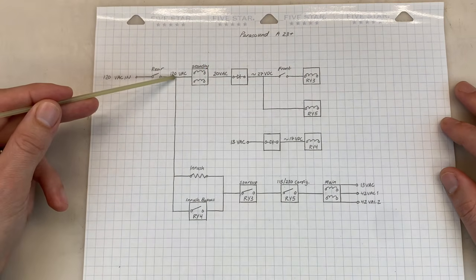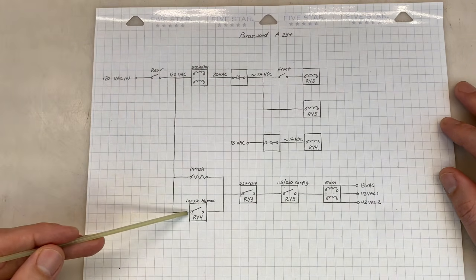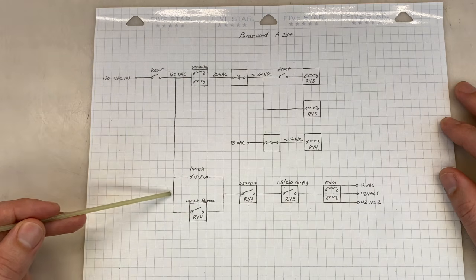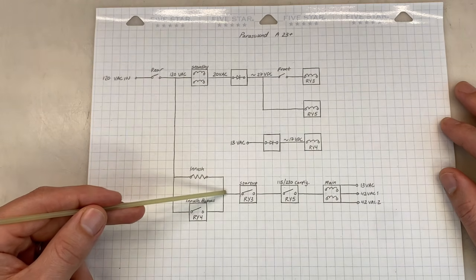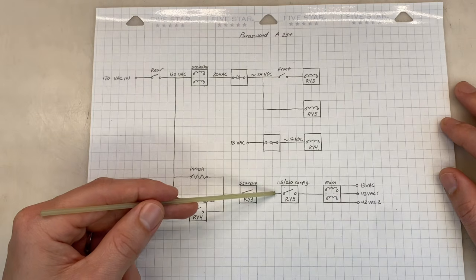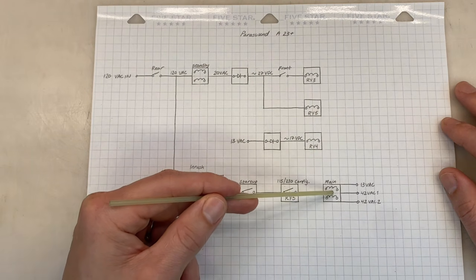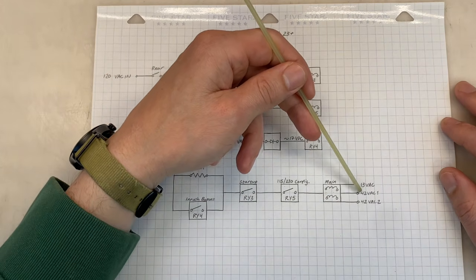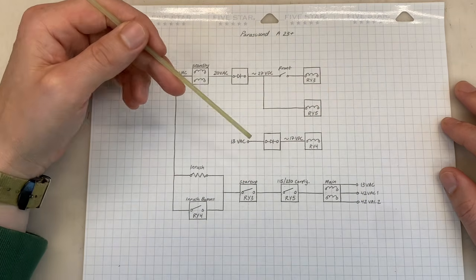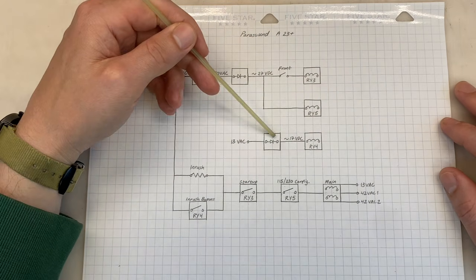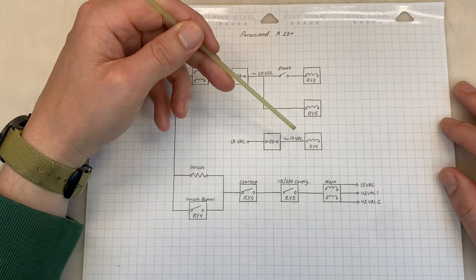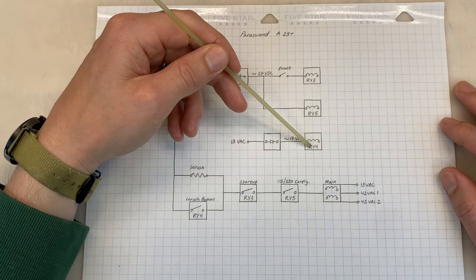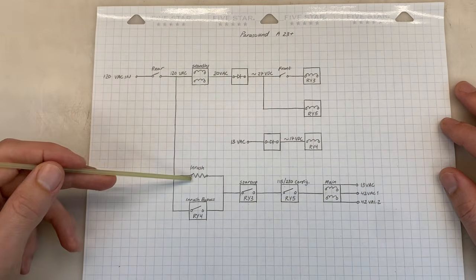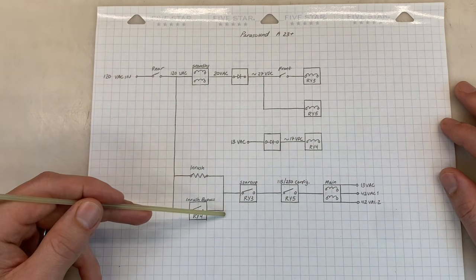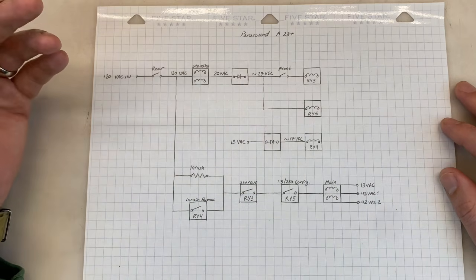Now let's come back to our second AC path. First, if RY4 was energized, it will travel through these contacts, but it's not yet. So it'll travel through this inrush current limiter. It'll then travel through the contacts of RY3, contacts of RY5, and finally it should energize the main transformer. Once this is energized, it will produce 3 voltages, 13, 42, and 42. The 13 volts AC will be rectified, which should produce something like 17 volts of DC. And this will energize relay RY4. Now that RY4 is energized, we can bypass this inrush current limiter, travel through the contacts of RY4, 3, and 5 for sustained power.